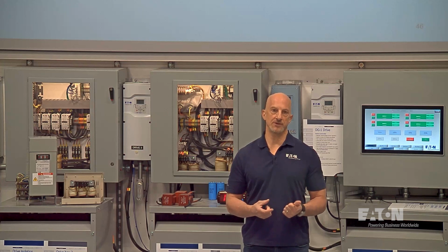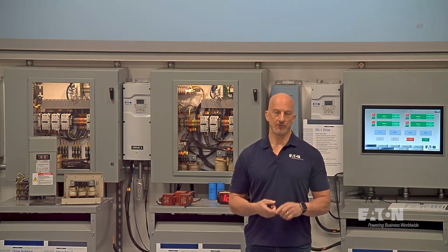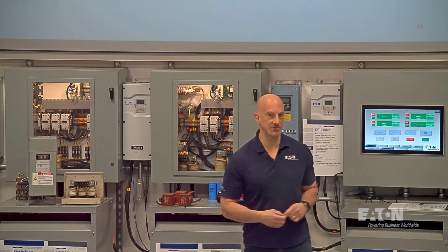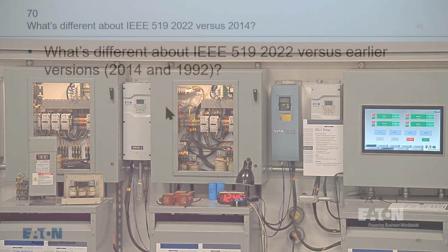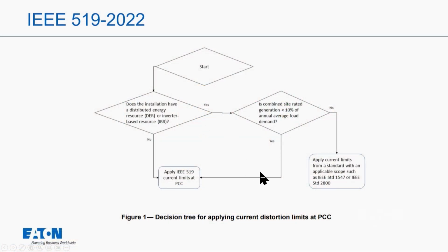The major difference in the 2022 one was around distributed energy resources. So let me show you something on a slide. This comes right out of the standard, and basically it's just a simple flow chart. It says, does the installation have distributed energy resources or inverter-based resources on board? And if yes, is the combination of that less than 10% of the annual average load? If yes, don't worry about it. Just apply the IEEE 519 standard as it normally would.